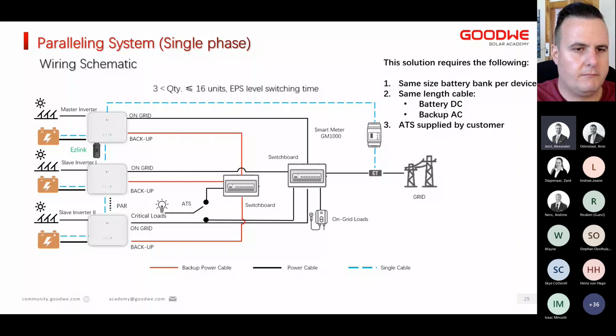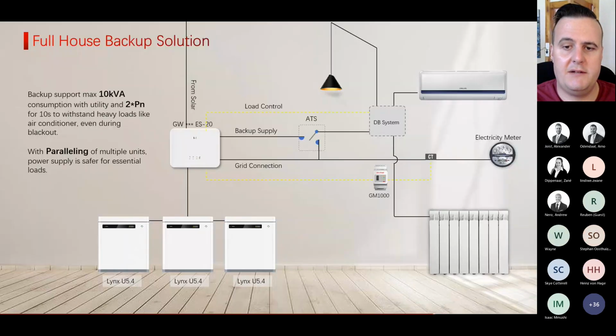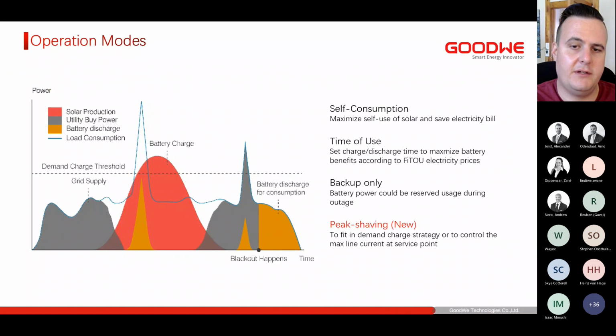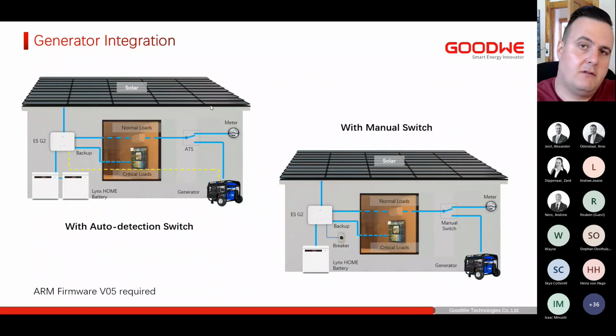Okay, so the unit can start in an off-grid environment through the battery or PV. Yes, and that's also why you have the generator capabilities, so that you can switch in a generator when you need to, especially in off-grid scenarios. When you have bad weather for a week, you're going to run out of power sooner or later, and that's why you need a generator in fully off-grid scenarios, unless you don't mind being without power for a day or two if we have very bad weather for a week where there's no solar.